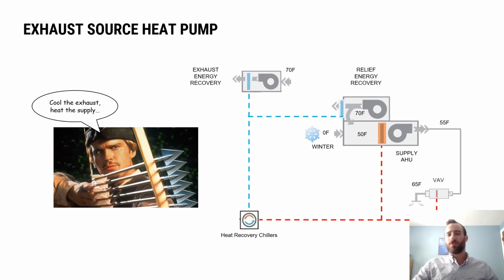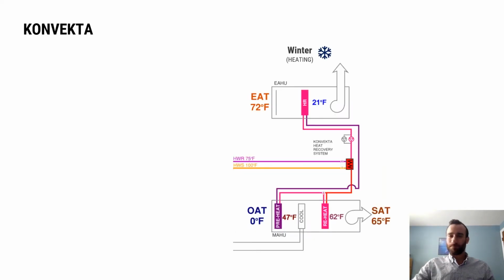So in its most simple form, an exhaust source heat pump looks like this. We can put a cooling coil in an exhaust air handler, and we can put a heating coil in the supply air handler or in the building in a VAV box, and we connect those with a heat recovery chiller, which is a water-to-water heat pump. We cool the exhaust and we heat the supply, kind of a Robin Hood type scenario there.